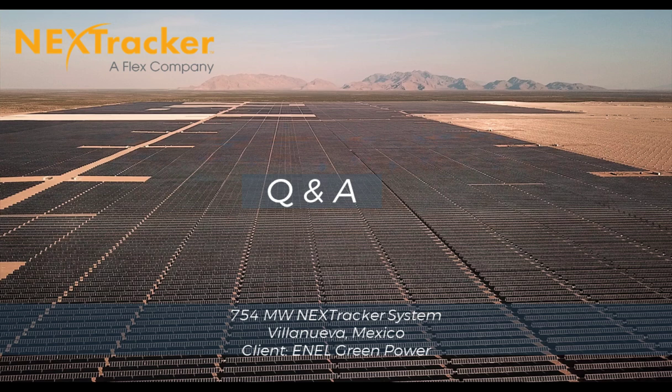On all NEXTracker systems, we have multiple weather stations already deployed and communicating with our wireless mesh network system. So we already have the infrastructure to be able to collect real-time information with a high degree of accuracy and reliability. What we're doing is we're basically adding pyranometers on site and then using that to characterize the irradiance and control it in real time. And so we buffer. You don't want the array moving around too much, so we do some buffering for a reasonable period, which gets us most of the way to the entitlement.